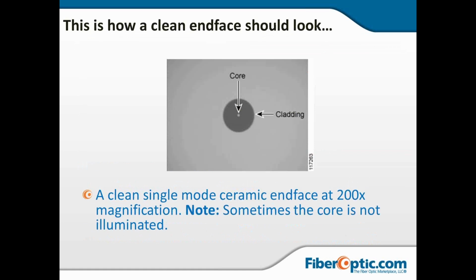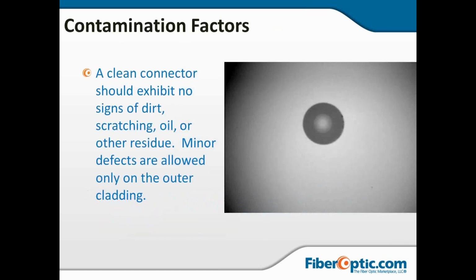All right, so a clean connector. A clean connector should look like this. You see the core and the cladding. Now, of course, the core is not always going to be illuminated. You won't always see it. It will depend on the environment that the other end of the fiber is residing. But a clean connector should have no dust, no scratches, no marks. It should be free of all dirt, scratching, oil, any kind of residue. Minor defects are allowed on the outer cladding. So you can see a little bit of the epoxy ring right here. Those are allowable, but nothing much more than that.